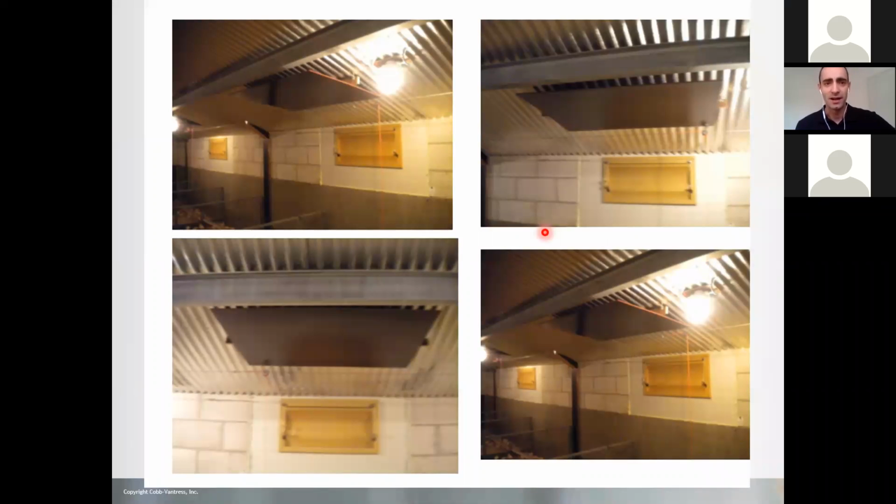So here you can see it a bit nicer. In this example, they've got this big metal I-beam, and if this deflector wasn't here, that air would have just gone up. It's going to cause disruption of the airflow against this beam. So what they did was put this nice piece of plywood or some wood material over here, and that makes a nice sort of deflector for that air to move smoothly past that and then get to the peak of the house. Again, smoke in your house is the best tool that you can use to make sure that you're getting correct airflow.